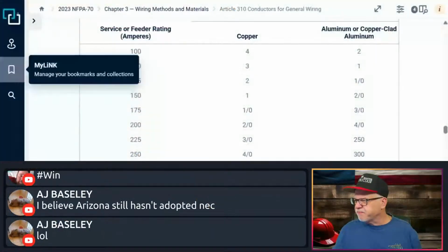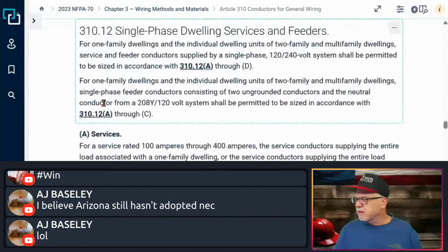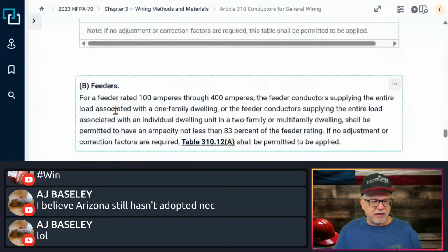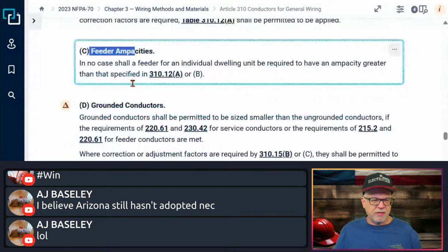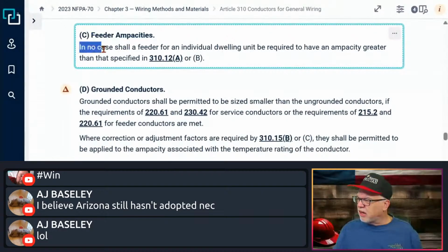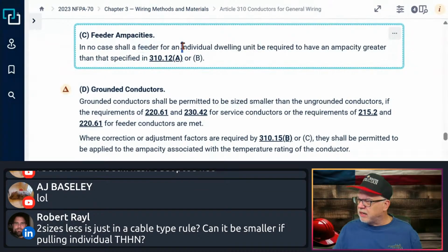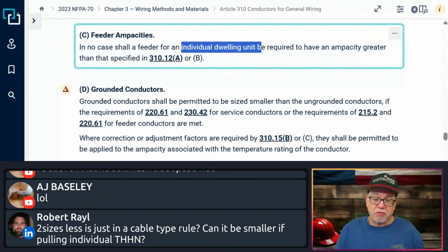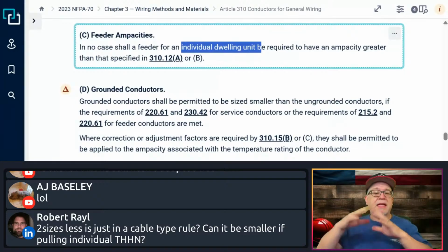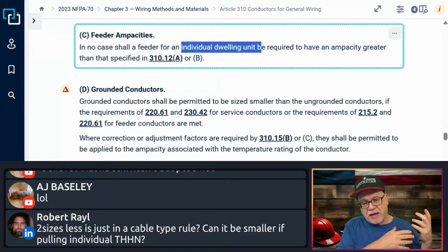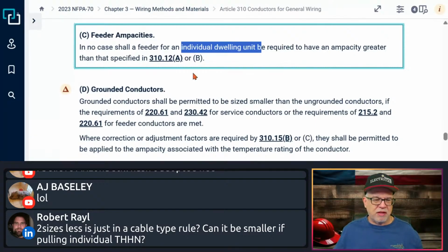So let's go to the NEC real quick. All right, and this right here, feeder ampacities. Okay, whoops, I don't know if you can see it right here. The feeder ampacities, okay? It says, in no case shall the feeder for an individual dwelling unit be required to have an ampacity greater than that specified in 310.12(A) or (B). So if I have a feeder going out to an individual dwelling unit, then again, it is not required to be larger than what would have been required per calculating in 310.12(A) or (B). So that's just saying, that feeder going out, there's no sense in making that much larger than the calculation you would have had supplying it upstream. It makes no sense to do that.